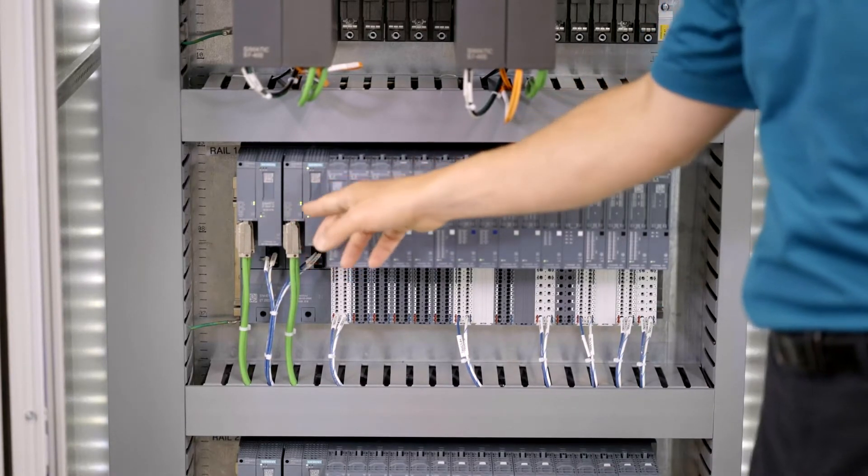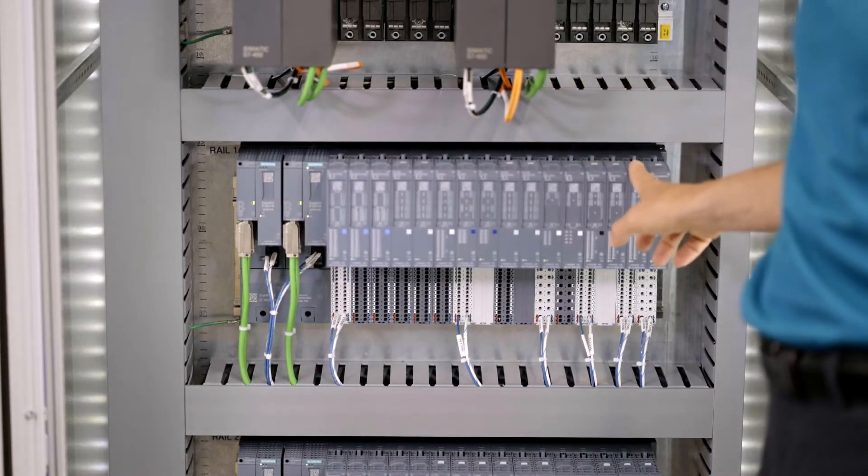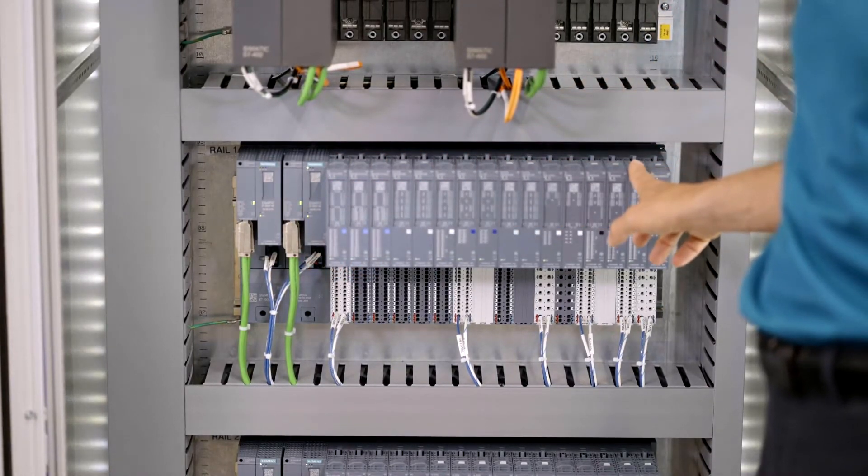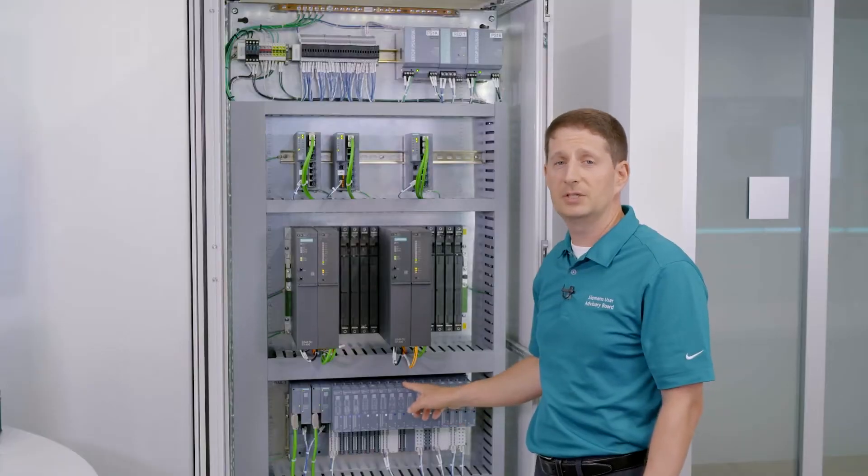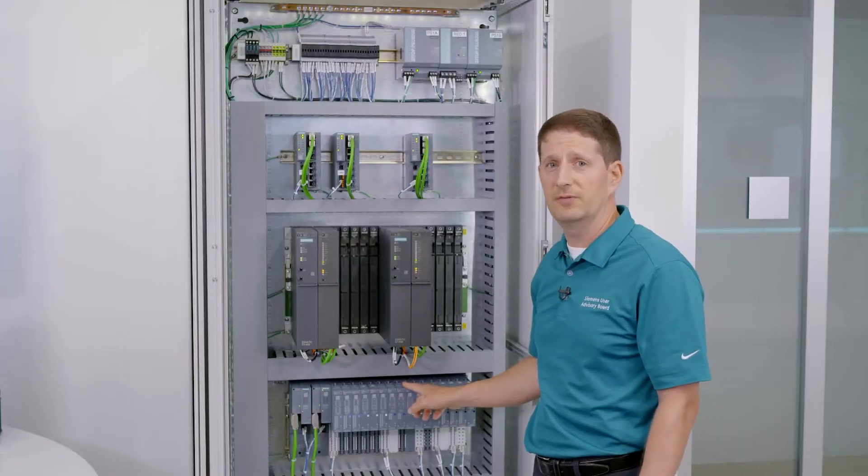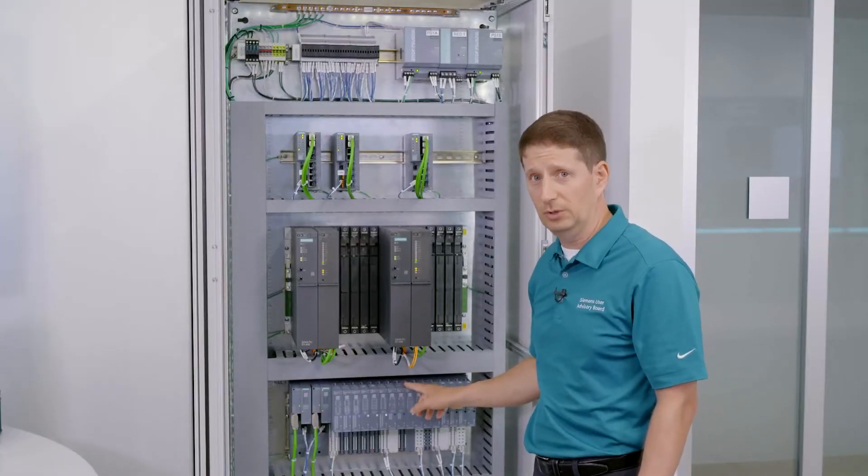You can extend this here. This I/O rail can be up to 56 I/O cards. It's rated from minus 40 to plus 70. It is conformally coated.